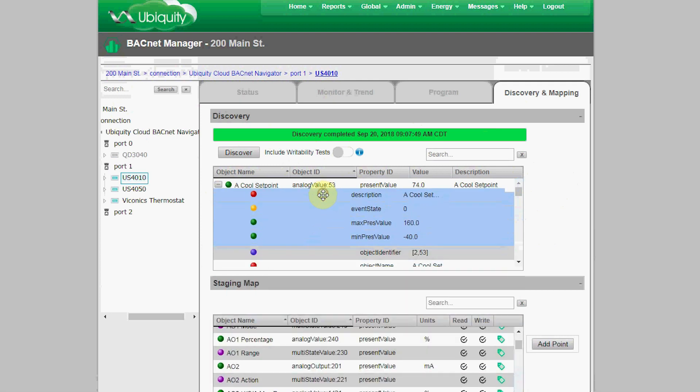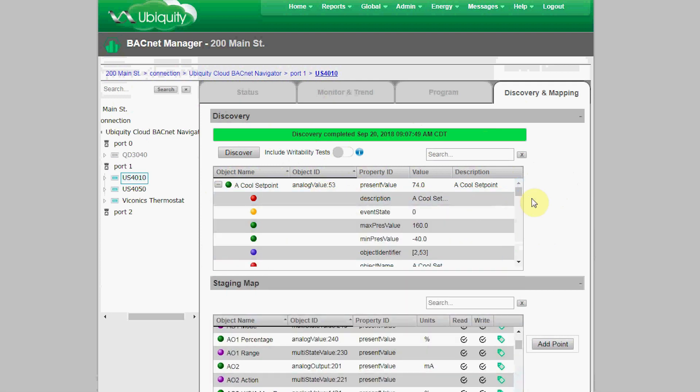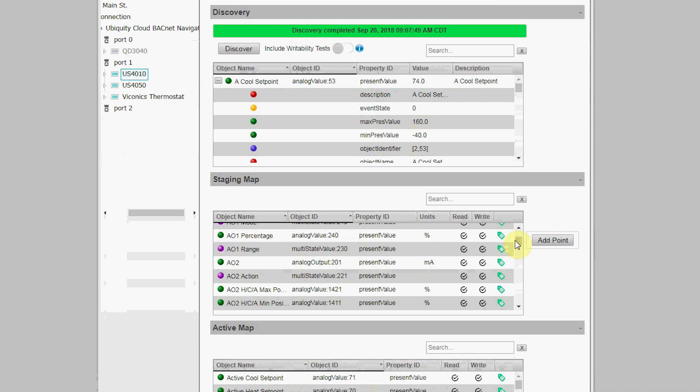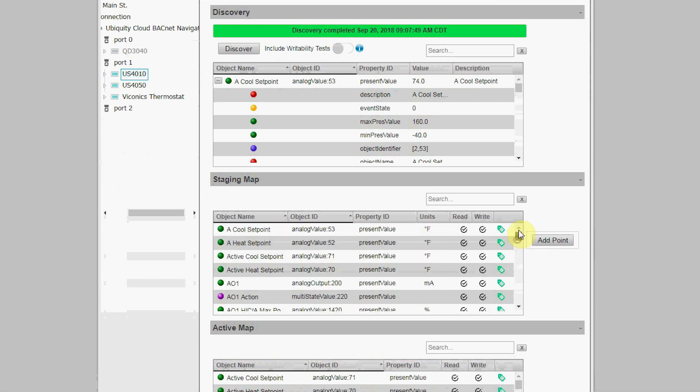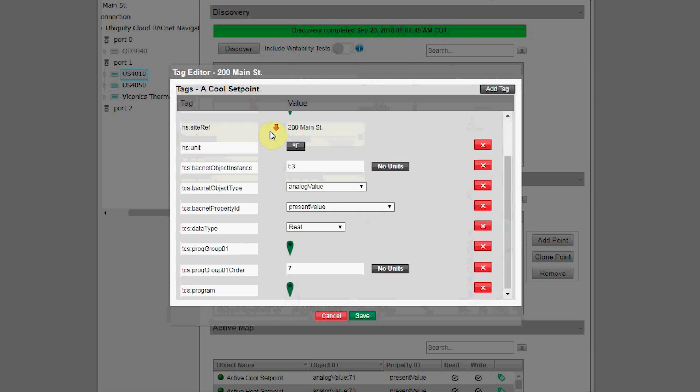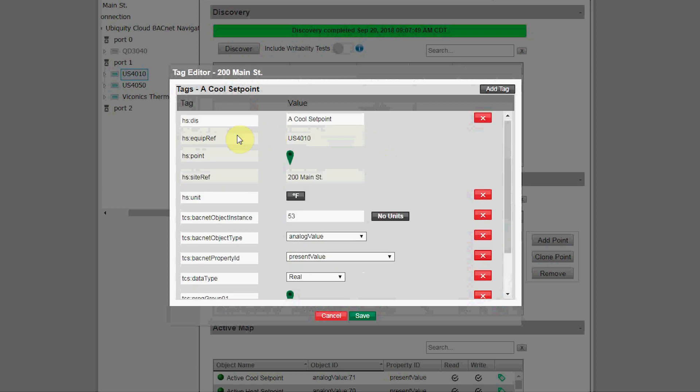If you need to bring in some associated properties other than present value, you need to open up the present value object, highlight those properties, and then drag and drop those in as well. Once in the Staging Map, you'll be able to see if the object is read-only or read and write, and have access to the tagging feature on that object. You click on the tagging icon and this opens up the tag editor.